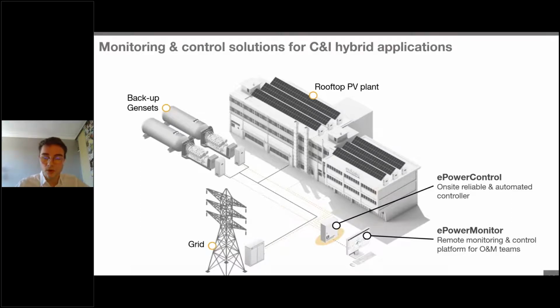It's very important to know that Elum's product is quite particular because you have this ePower Control main component installed on site that is physically connected to each of the power units to be monitored and controlled, and that operates the system live. It means you have this main component that is autonomous, that can be operating also during grid outage - we have UPS - but also during internet outage. You do not need this component to be connected to the internet to manage your site.